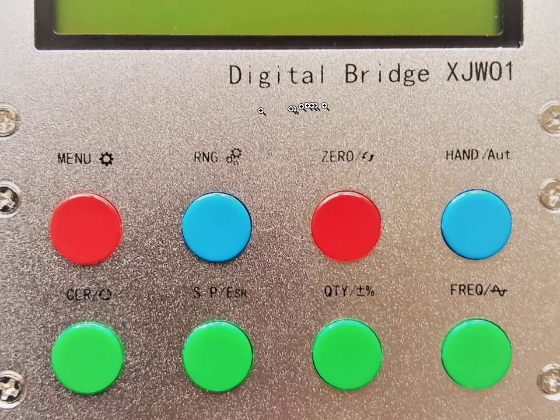So I should mention that when you press these buttons, because of the software polling that's used, they don't always register. So you mustn't press them too quickly. Press them for about 1/3 of a second and then release. If you press them really quickly, it will miss your key press, and then you'll become confused as about what's actually happened.